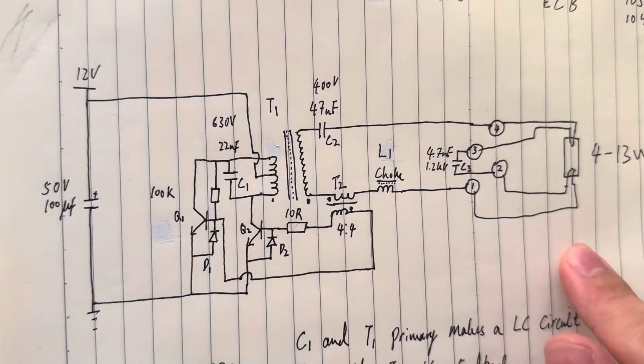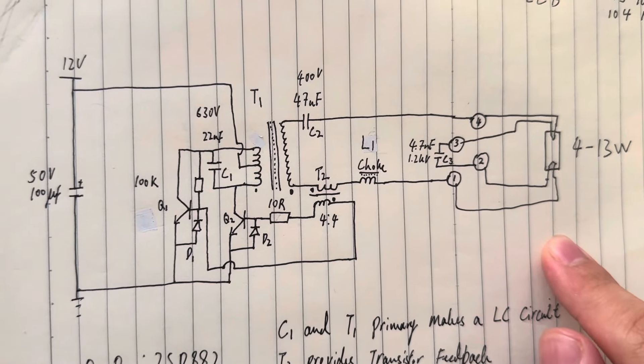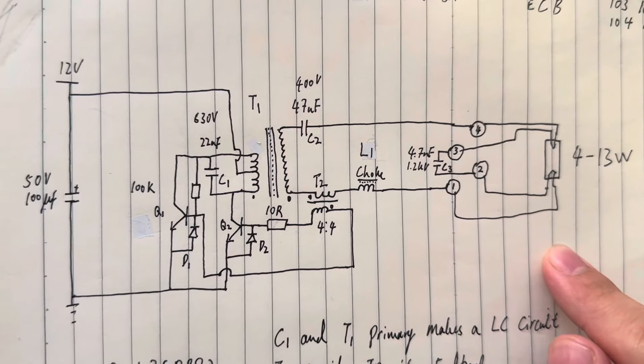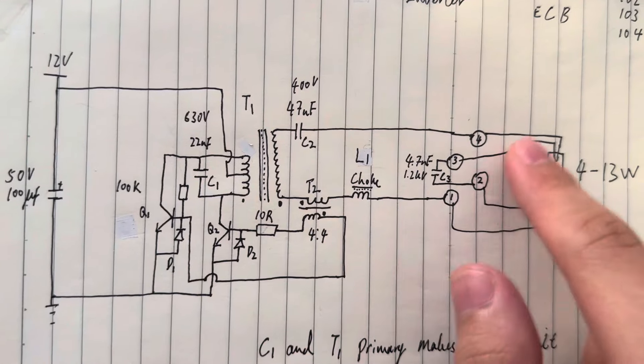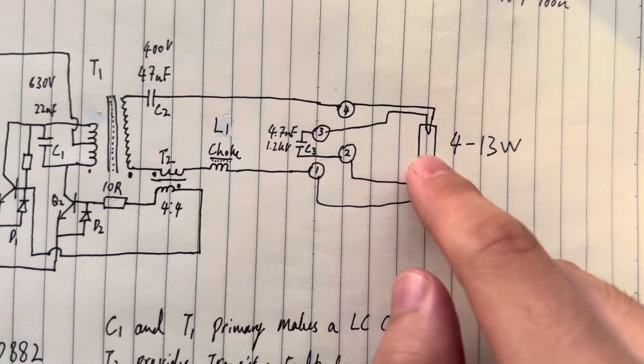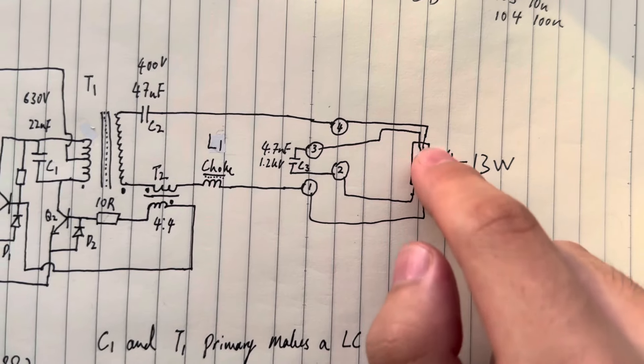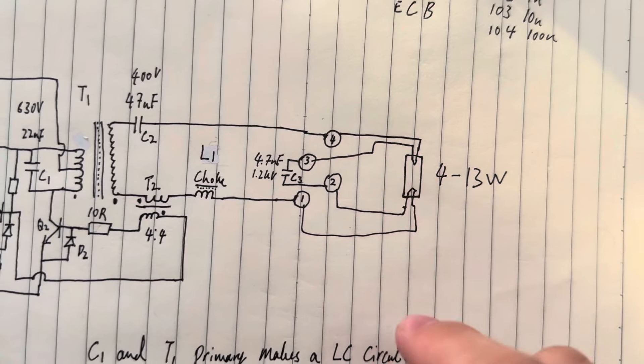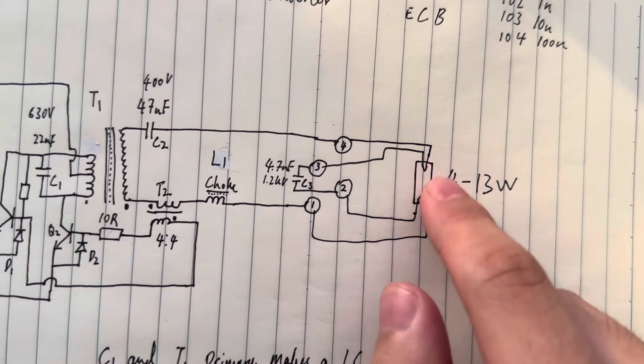And so, for the failure of this circuitry, it's actually really easy to repair. Generally, what could happen if the ballast failed, is that if the lamp itself breaks, the glass broke, basically what will happen is that the arc would not initiate throughout the entire discharge tube.